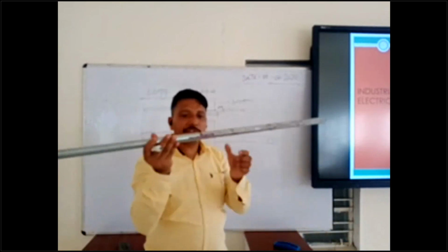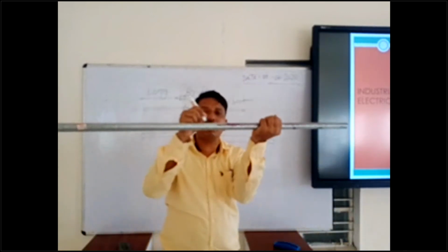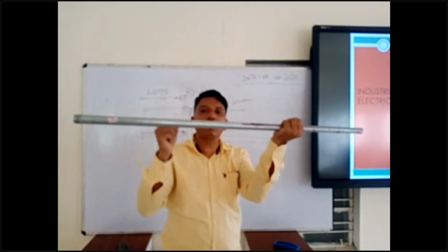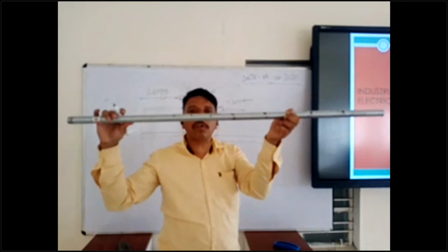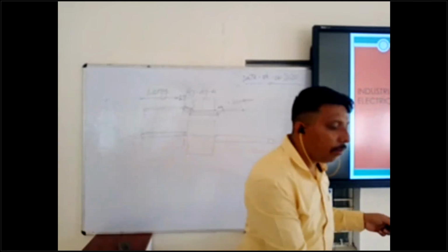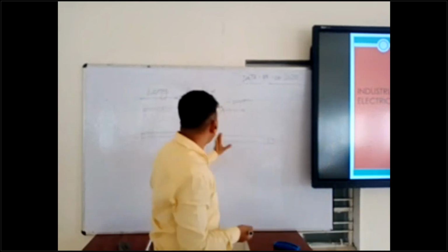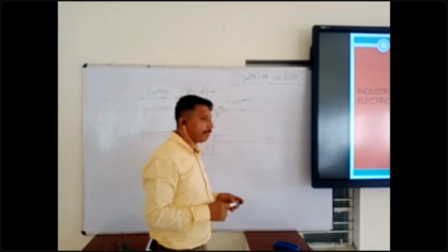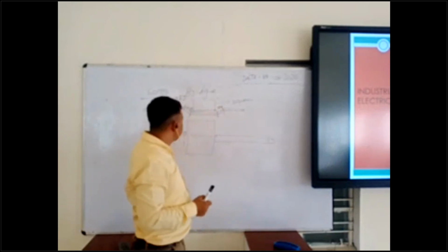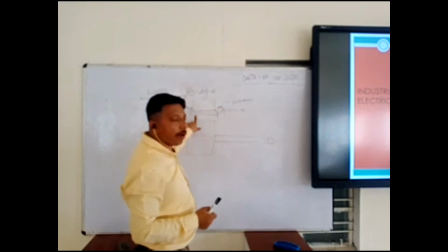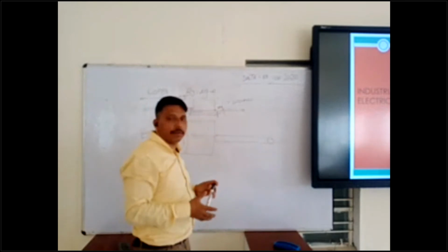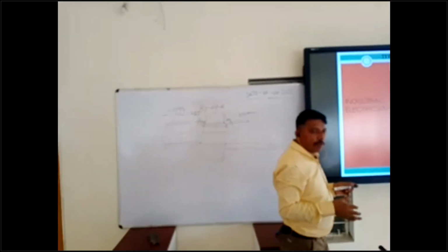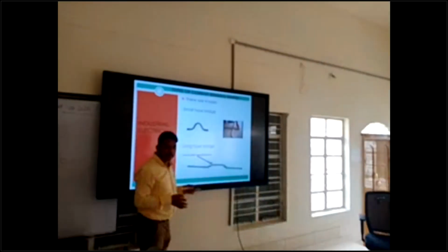So the straight pipe is this one, and you can mark it. Suppose this is the center: first, second, and third. You mark it like that, 4 for the long bridge and only 3 for the small bridge. Small bridge bend comes with 3, long bridge bend comes with 4. Okay, clear? Clear about long bridge and small bridge? The difference is only in the cutting parts.